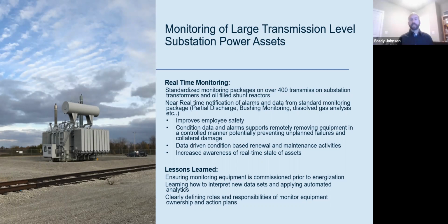Units failed catastrophically right during energization, and our monitoring equipment was installed, but the alarms weren't going back to operations. It was a hard lesson learned — our equipment did pick it up and sent off the alarms, but they weren't going anywhere. So we had no idea, no one was informed, and we could have prevented that. We gained a known signature from that event and added it to our lessons learned. So, getting into how you interpret that data...